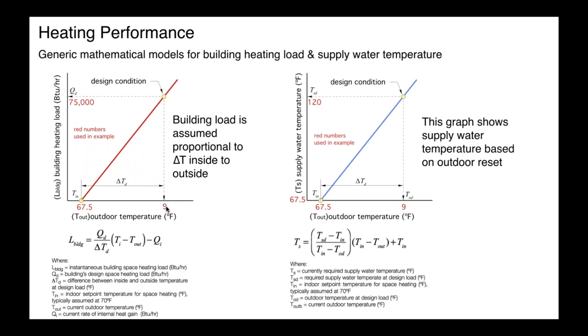And then one more model we need. We need to have a relationship between the water temperature that needs to be supplied by the heat pump to the distribution system, to the heat emitters, based on how cold it is outside. And this goes back to a very fundamental idea in hydronics called outdoor reset control. Simply, as it gets warmer outside, the water temperature requirement goes down and vice versa. So in, again, this corresponds to this building in Boston. The distribution system needs 120 degree water at design load conditions, corresponding to that outdoor temperature of 9 degrees, and that water temperature goes down as we get warmer and warmer.